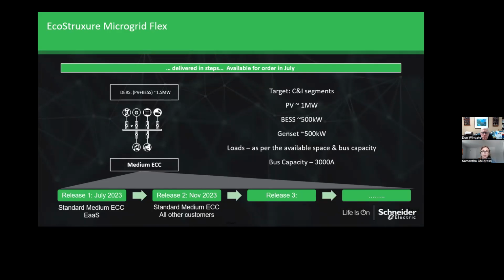Small to medium buildings that can achieve up to 1 megawatt of solar photovoltaic installation—that's 1 megawatt AC. A battery can accomplish about 500 kilowatts of storage; may not have to go that high, but that's where this sized ECC tops out. Our generator is also at 500 kilowatts, used in lieu of the utility during a power outage—the generator turns on and acts like your typical utility source. Loads can be configurable up to the available space and remaining bus ampacity.